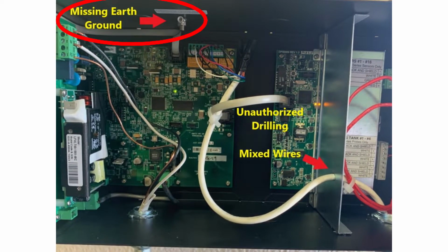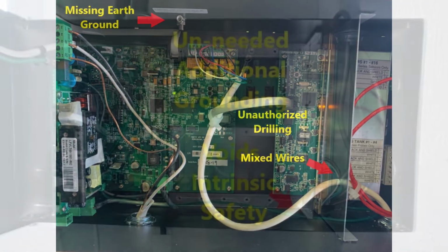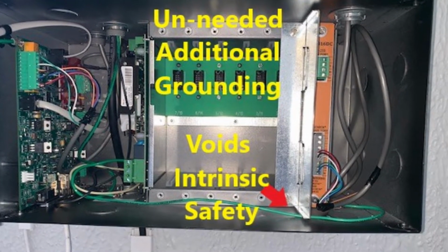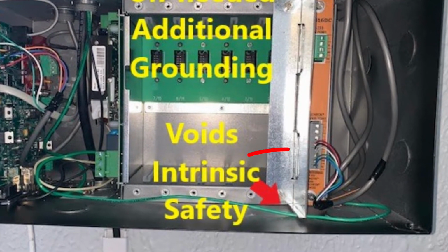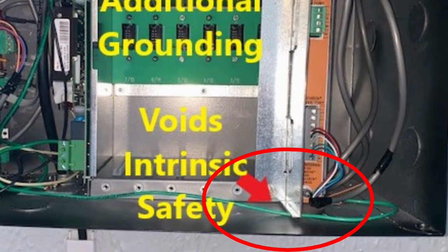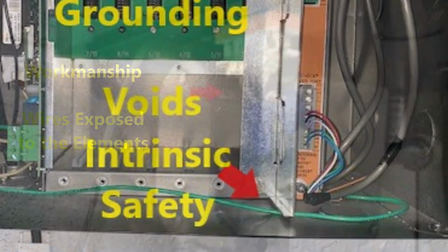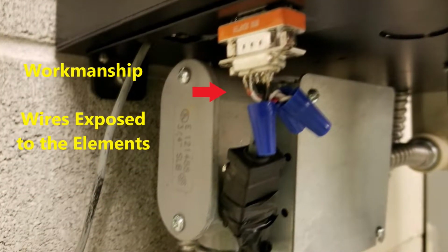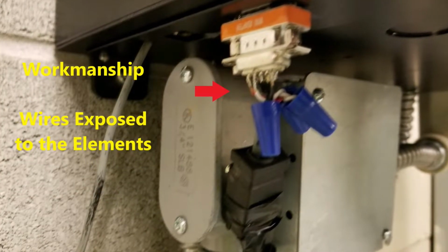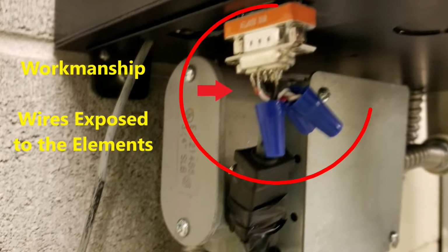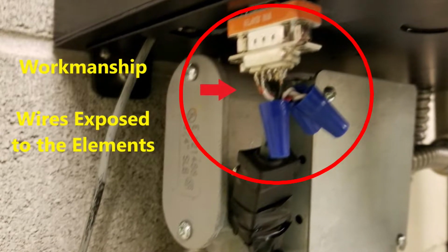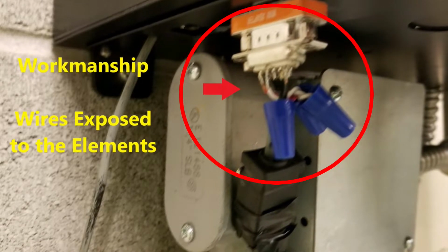Also noted was the lack of a separate earth ground. Here the technician thought the wireless receiver needed an earth ground. Running the wire under the metal barrier reduces the intrinsic safety. Sometimes we don't have all the correct items needed to make a proper communication connection. Here the wiring is a mix of splices, leaving the connection exposed to the elements.